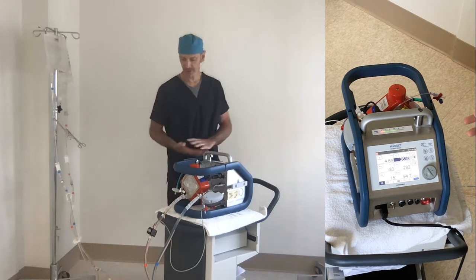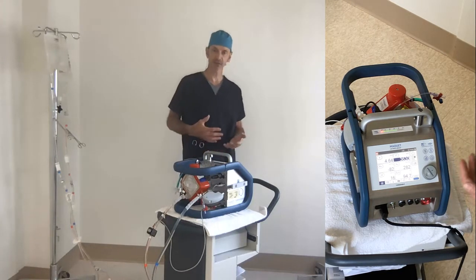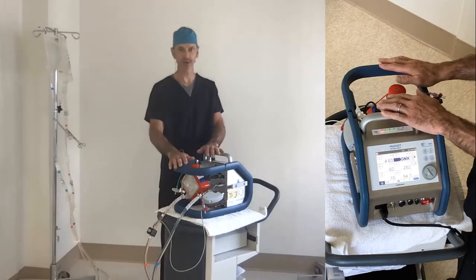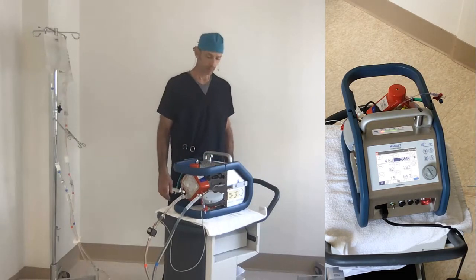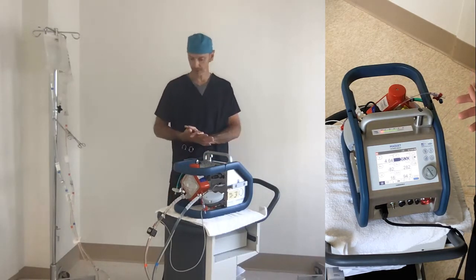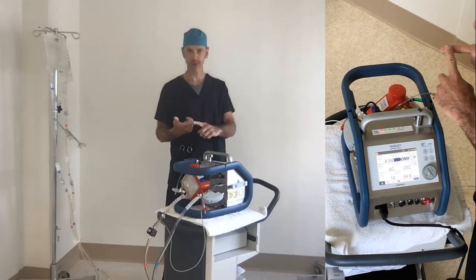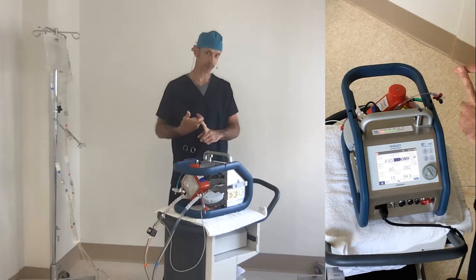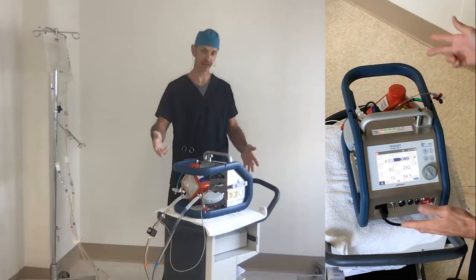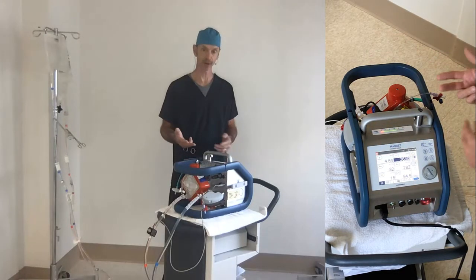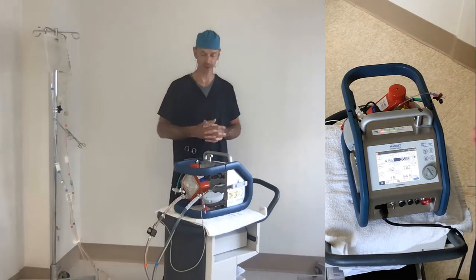Okay, so we're talking about pump failures. Let's start with the simpler stuff. Pump stop. What could cause this pump to stop? There are 2 things that will cause this pump to stop: bubbles and pressure. The third thing would be some cataclysmic failure that you can't repair. But bubbles and pressure are things that you can address.